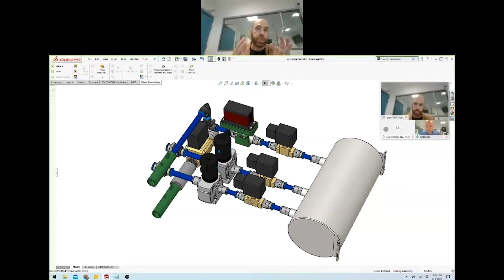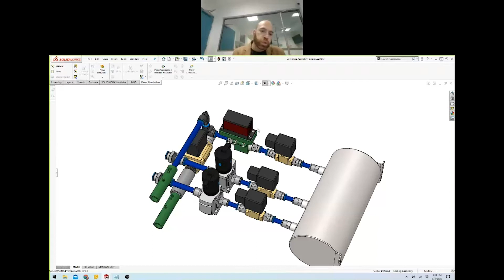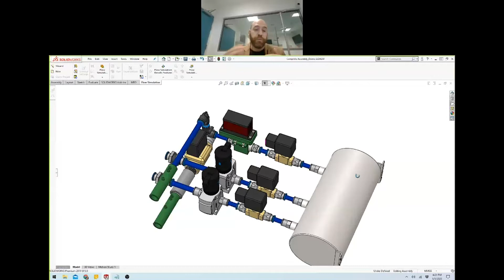Now, to go to the ventilator in a nutshell, the ventilator typically has a couple of operation modes. We're not going to go into details on every single one of them, but let's talk about the main ones. There is the pressure control. So this is the ventilator: the machine will pull air inside the lungs of the patient and try to reach a certain pressure point. There is volume control, where the ventilator will push air until it reaches a certain volume.